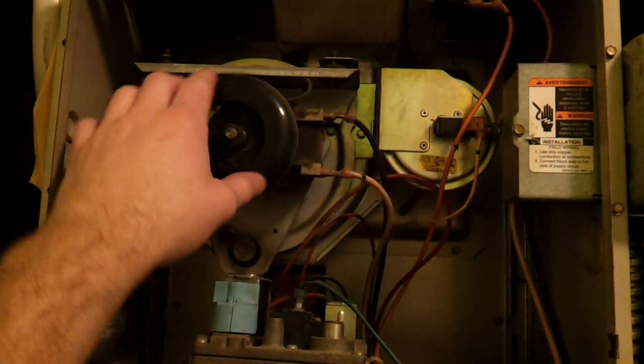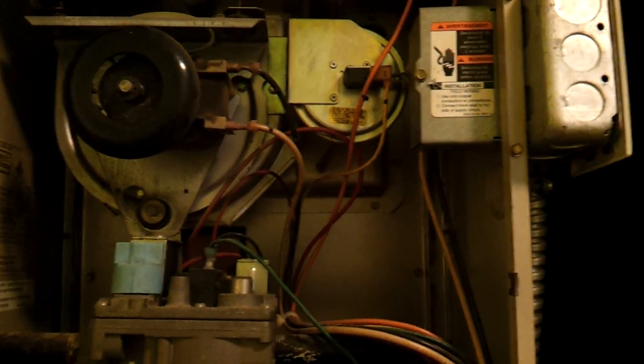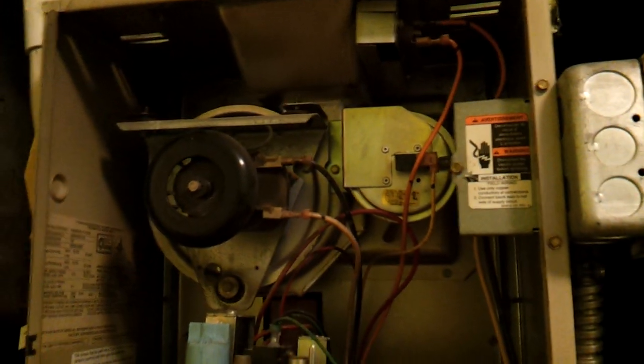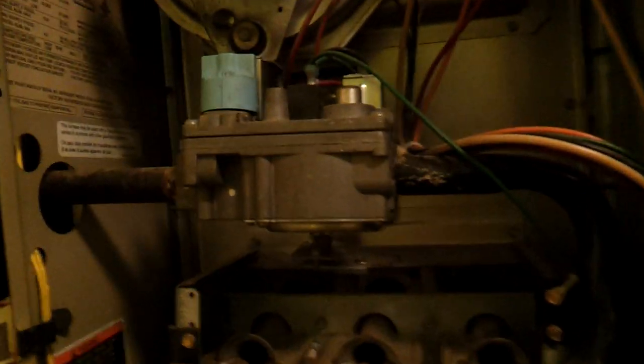We've got the draft inducer, which pulls the gases to the heat exchanger, which is there in the back. Pressure switch, which makes sure the draft inducer is actually running. Got a Carrier's proprietary blocked vent system here, which I call draft guard, and that is in case the exhaust pipe gets blocked. It'll start spilling exhaust gases out this little hole right here, and it'll trip the switch, shut it off. Got our redundant gas valve here. I believe it's a White Rodgers gas valve.